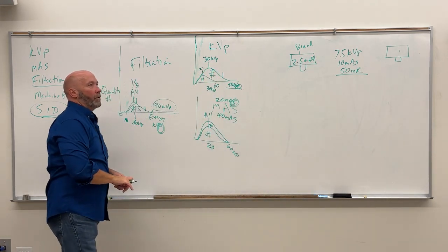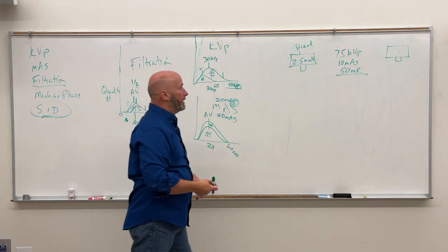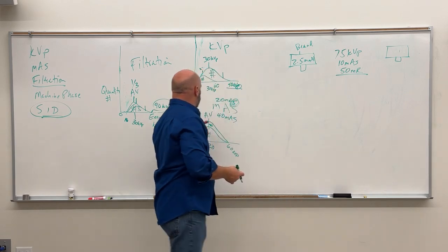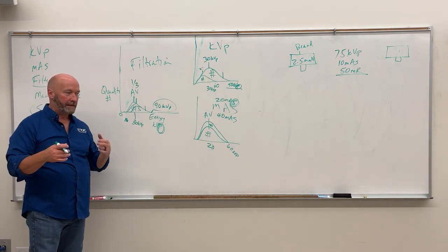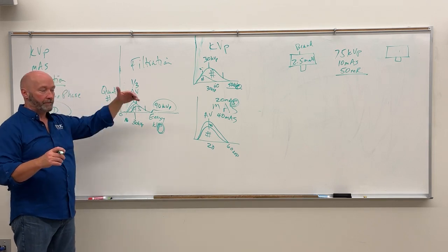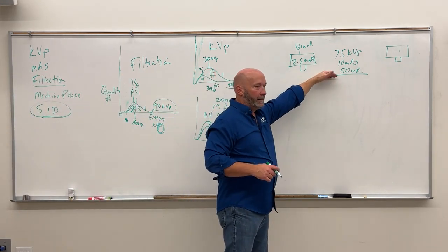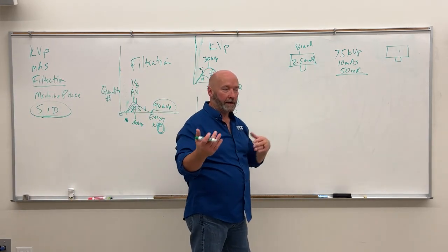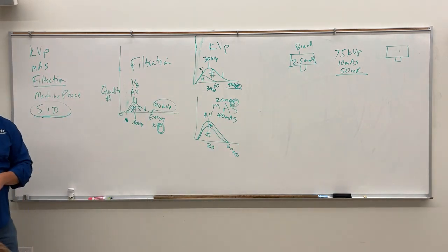So what happens as the tube ages? You get tanning, right? With tanning, because it's a type of filtration, we lose numbers. Every year, your biomed guy has to come in and make adjustments to your tube to make sure that your output, measured in radiation exposure in air, gray in air, or milliroentgens, remains the same.